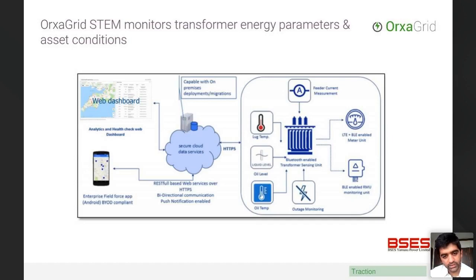We install a STEM device that does all of these measurements, whether it is feeder current monitoring, outage monitoring, oil temperatures, oil level, lug temperature, any temperatures that are there on the transformers, as well as the loading on the transformer. All those inputs are acquired and then sent to the cloud platform. And once the data is on the cloud, we show it on the web tools.